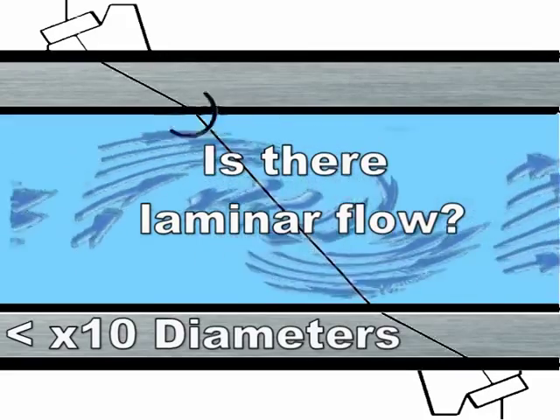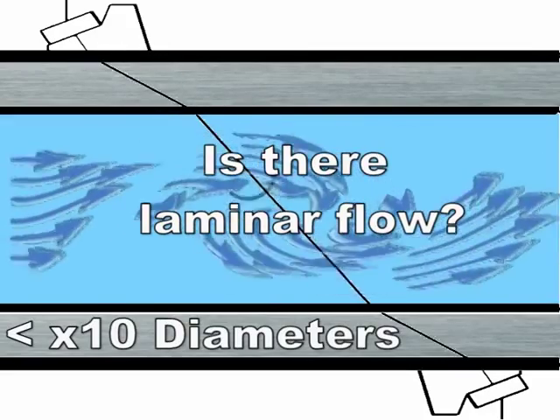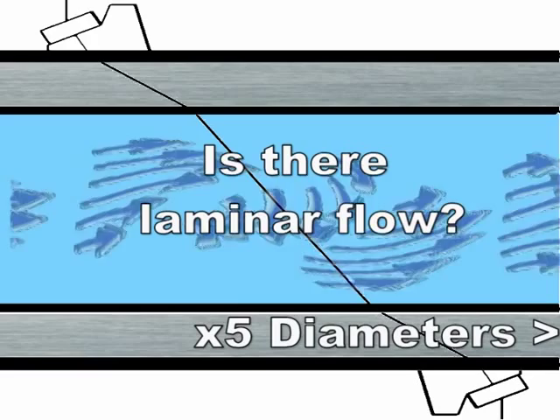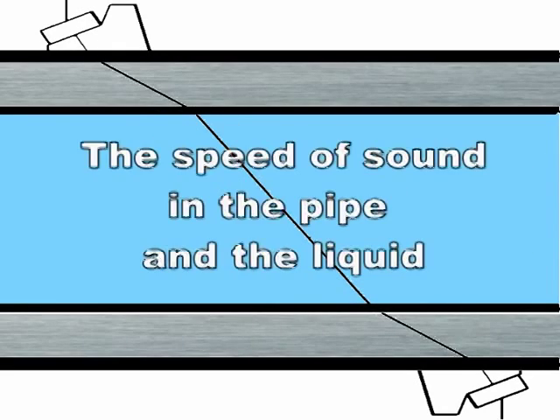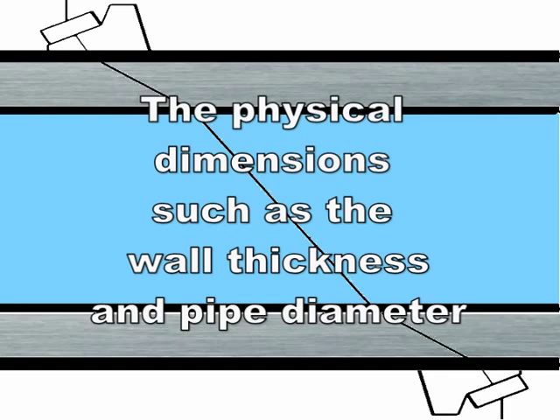Typically, you'll have laminar flow when you have 10 diameters upstream and 5 diameters downstream from the flow meter clear of any obstructions. We need to know the speed of sound in the pipe and the liquid for the refraction angle calculation, and the physical dimensions such as wall thickness and pipe diameter.